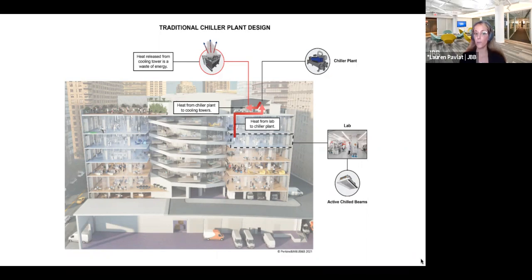That heat is then taken to the chiller plant on the roof, where it would typically go to the cooling towers and get released. In this scenario, the heat released from the cooling towers is a waste of energy. It's released because it's low-grade water, and we just don't heat buildings with 120-degree hot water. But with reducing and recycling in mind, this brings us to the question: how can we use that 120-degree hot water to heat a building? Why get rid of it? What can we do with it? This question is what brought us to our design for 125.